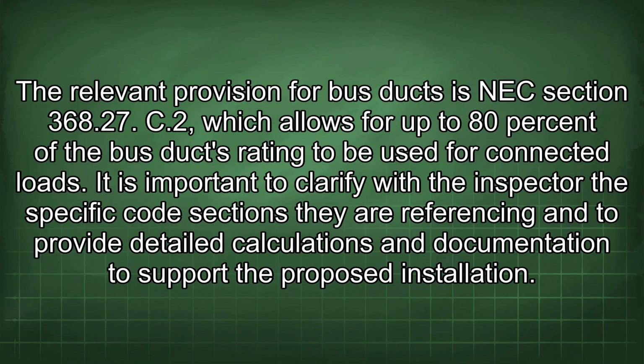The relevant provision for bus ducts is NEC section 368.27 C2, which allows for up to 80% of the bus duct's rating to be used for connected loads. It is important to clarify with the inspector the specific code sections they are referencing and to provide detailed calculations and documentation to support the proposed installation.